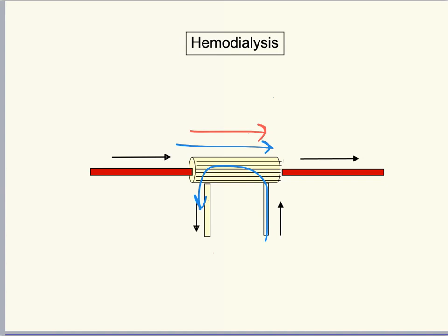Having dialysate flow in the opposite direction allows the blood at the end of the capillary to meet fresh dialysate containing zero urea and creatinine, thus allowing efficient diffusion to continue. Ultrafiltration can also be employed by adding negative pressure to the airtight dialysis cartridge and pulling plasma through the capillary pores to reduce the patient's extracellular volume. Hemodialysis is typically performed in sessions lasting 2 to 4 hours.